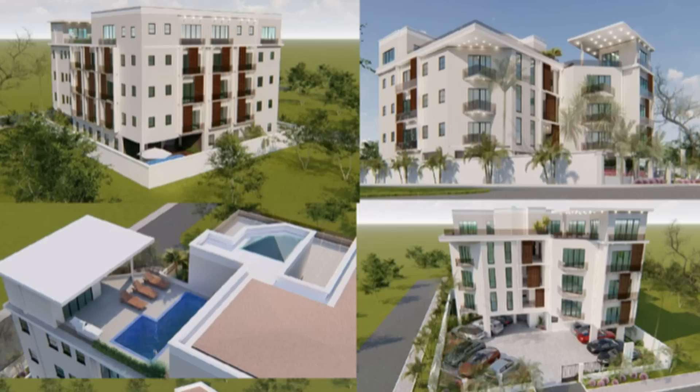Items like the water system, common area lighting, and water pumps are landlord services that serve the tenancy — the landlord generally pays for those, but there will be a service level agreement in the contract with a proportionate contribution from each tenant towards common services: cleaning, general water, lighting, and so on. Looking at this building, I've reviewed the electrical plans — the lighting design, sockets, and incoming infrastructure have all been done, although there are a few errors which is one of the reasons we've been brought in to correct and to construction-monitor the whole build.